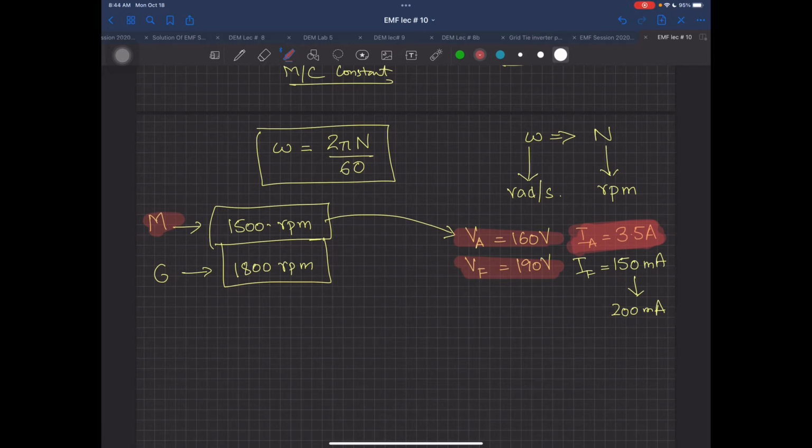But since in the lab, if you have seen this, you have a motor and a generator coupled together. So there is a load attached a little bit, even if the generator is not working. So there is a shaft, there is a moment which is actually working over there. So practically it will be taking some like 1.7, 1.8 ampere current, but when you are going to start your generator and start loading it, you are going to have this current. So there is a limitation of 3.5 ampere. If you will go beyond it, the armature winding will be damaged.